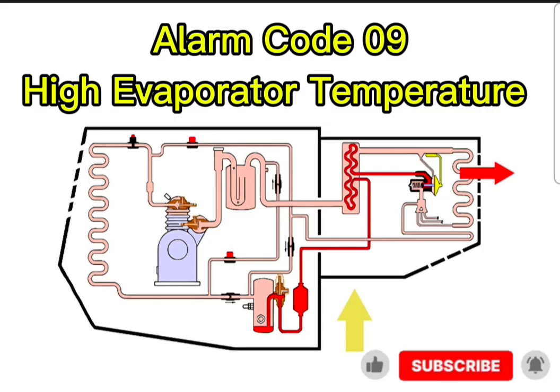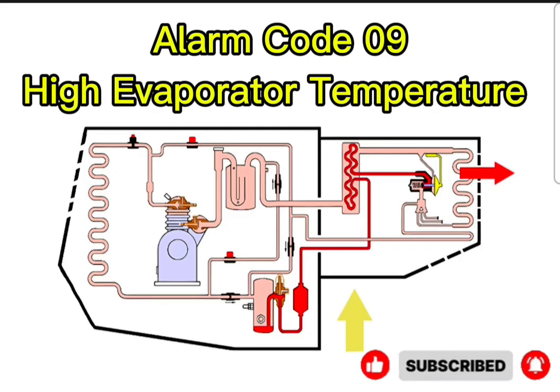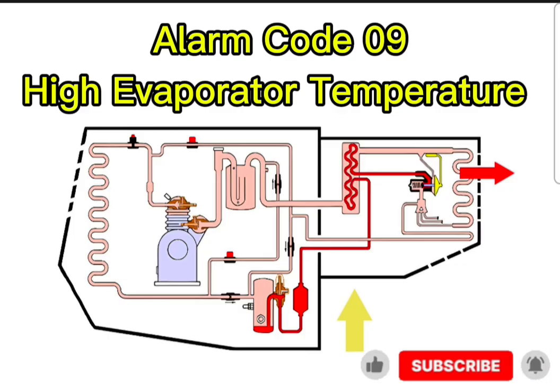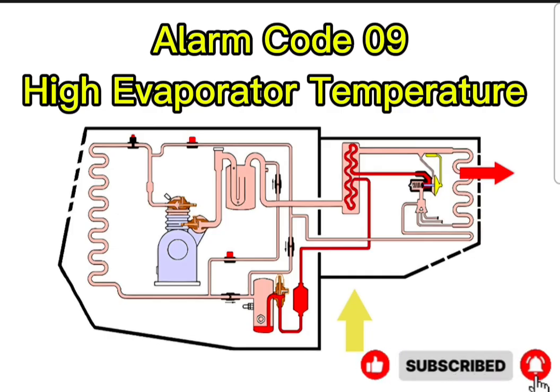The cycle is supposed to end, the hot gas solenoid is supposed to close, and the damper is supposed to swing back open to let the cold air flow again. Precisely. But if the physical hinges on that damper seize up, or the actuator motor burns out, that door stays permanently shut. And then the unit goes back into its heavy cooling cycle, but the cold air cannot escape the coil housing. Because it's blocked. The airflow is completely blocked by a metal door. The compressor is working furiously, generating massive mechanical heat on the back end, but the localized energy has nowhere to go. Wow. So the temperature inside that sealed-off section rockets up to 155 degrees. It's a mechanical failure of containment.